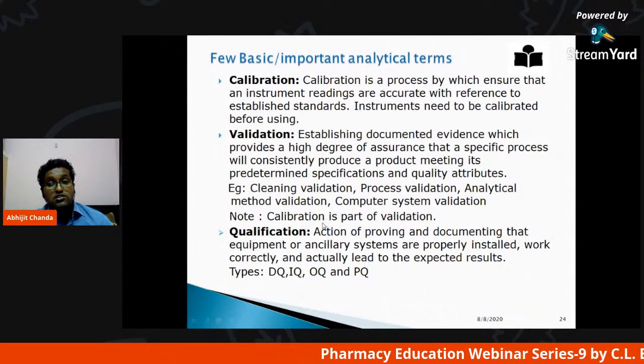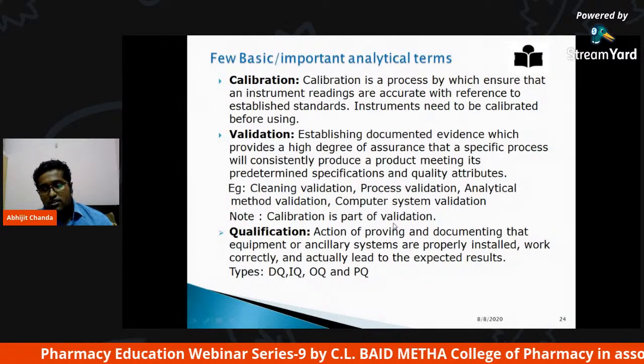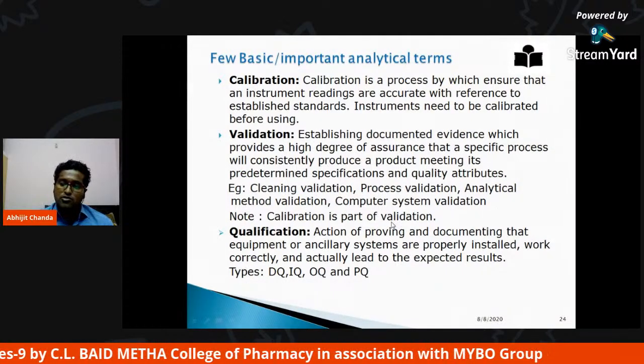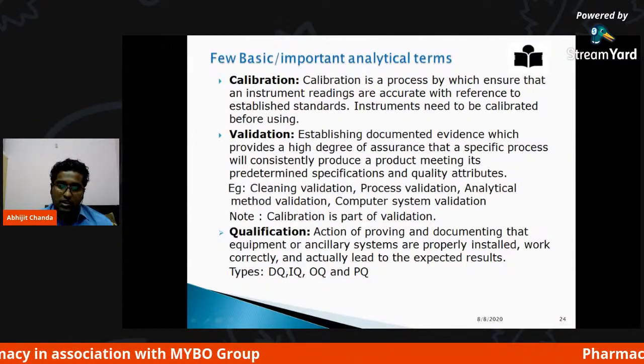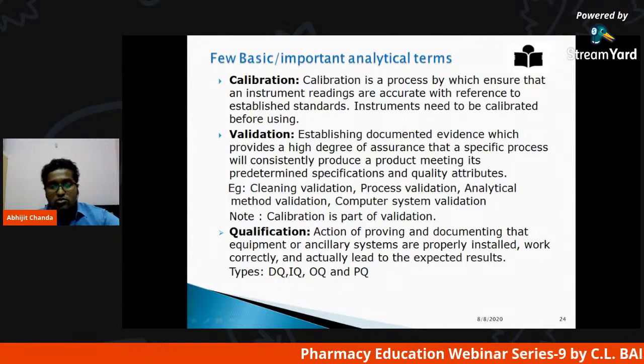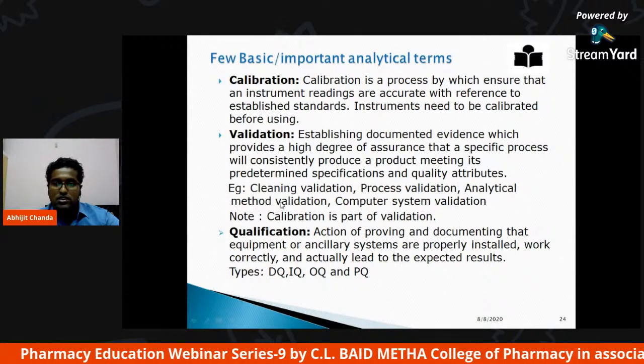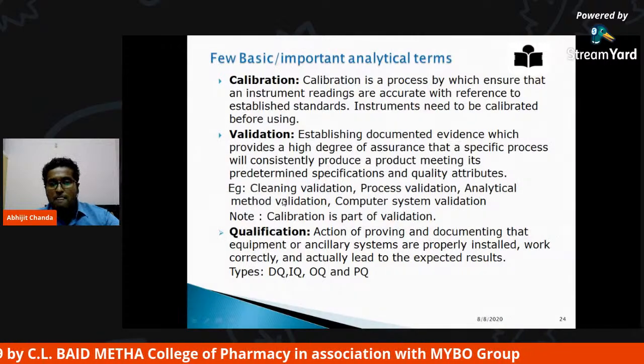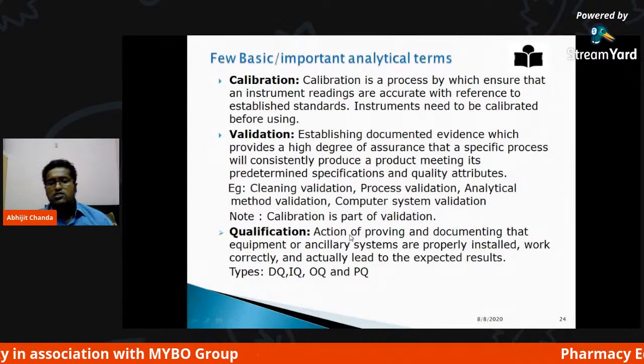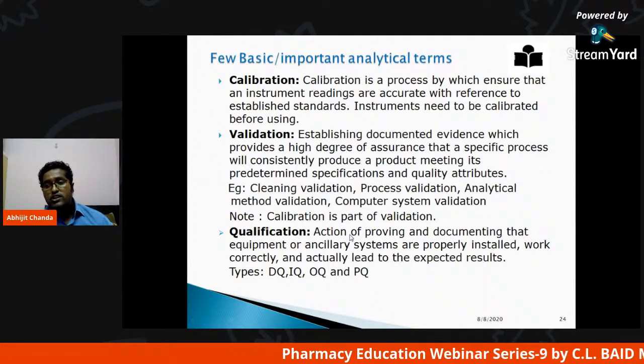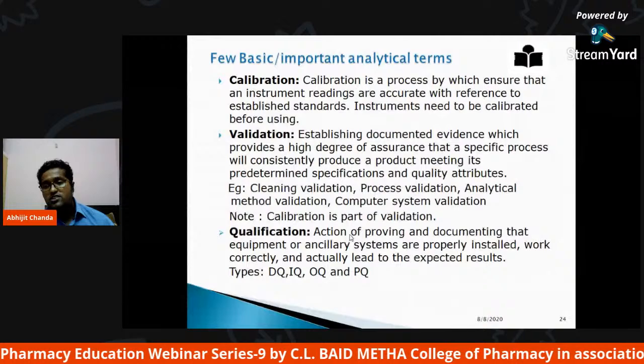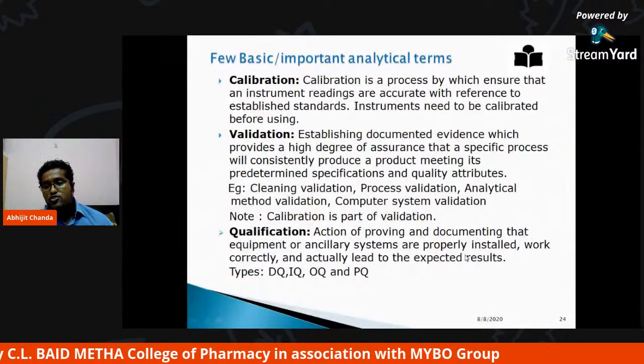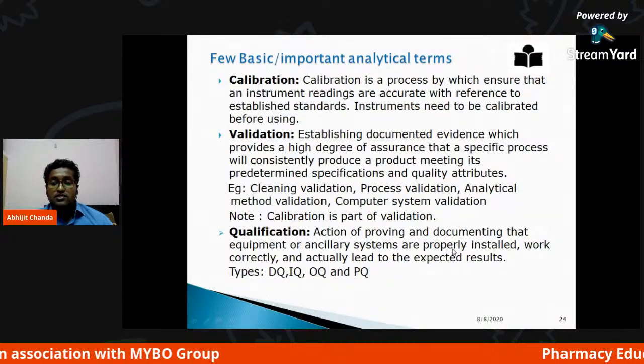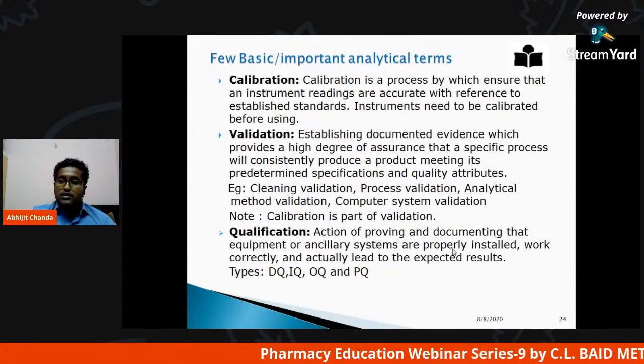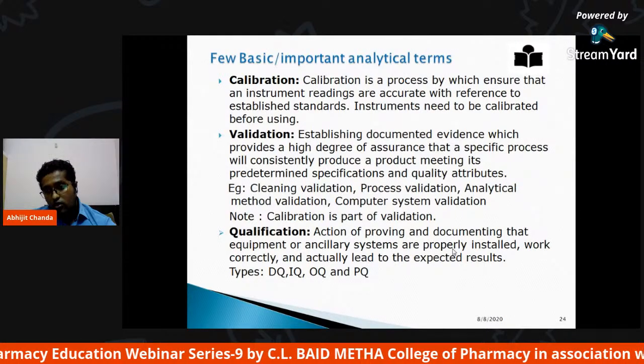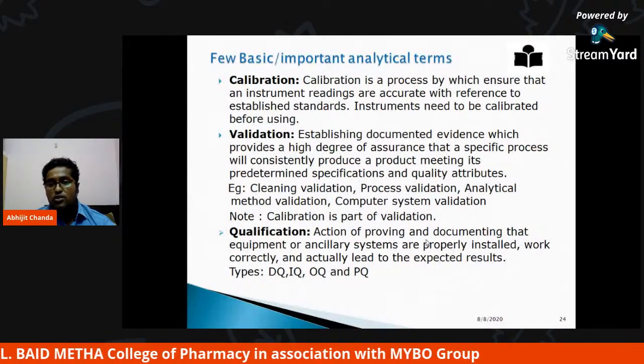Note here one thing: calibration is a part of validation. So before starting any activity in the pharmaceutical industry, especially in quality control and quality assurance, whatever instrument you will use has to be calibrated. Without a calibrated instrument, you cannot perform any task. Next, qualification. What is qualification? Qualification is nothing but the action of proving and documenting that equipment or ancillary systems are properly installed, work correctly, and actually lead to the expected results. Types: design qualification (DQ), then IQ installation qualification, then OQ operational qualification, then performance qualification.